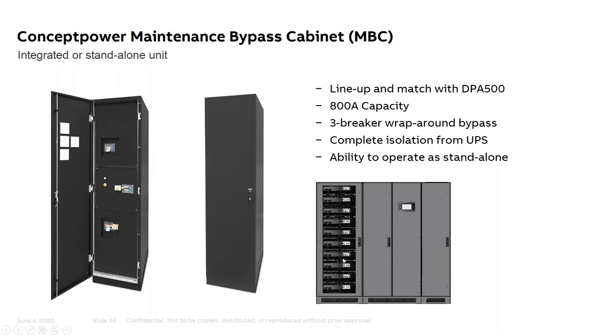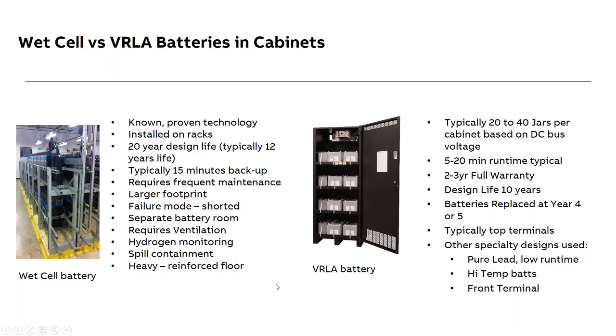So the picture here basically just shows a 500 kW modular UPS with a 3-breaker bypass bolted to the side. It looks nice. Other than that, this could be part of the surrounding switchboard or switchgear as well. And the energy storage, the battery, could be in a matching cabinet as well, making it one long lineup.